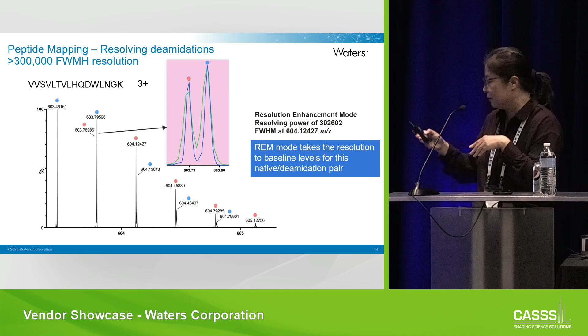And if you turn on the MRT mode, that's the multi-pass, multi-reflection mode, you can start seeing it being baseline resolved. So this is just to demonstrate the power of high mass resolution, what it can do to differentiate the co-eluting deamidated peptides. And from my recollection, I can see them being separated for ions as big as 1,000 AMU, a doubly charged peptide at m over z 1,000.